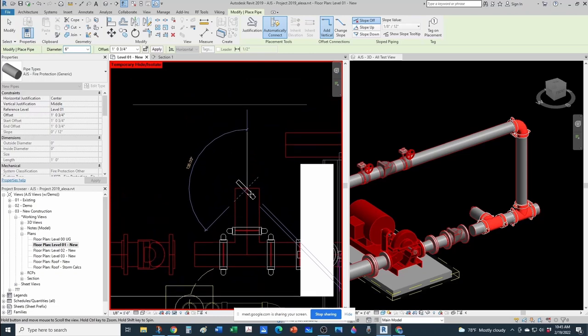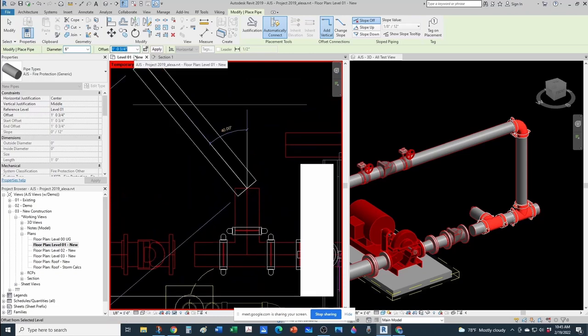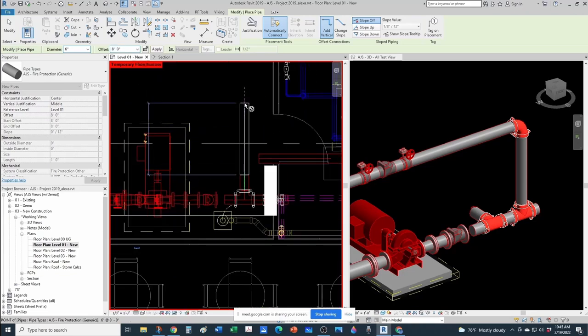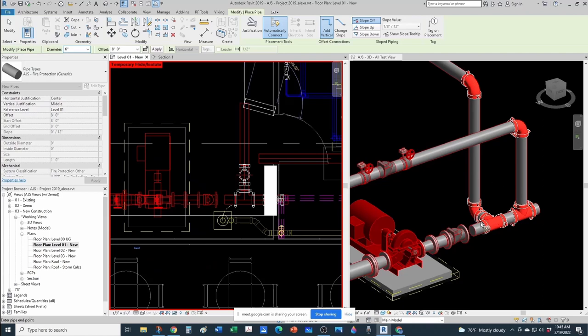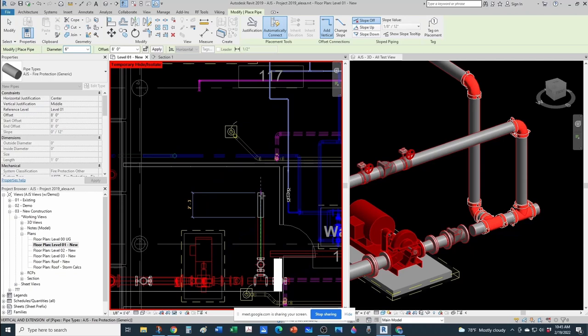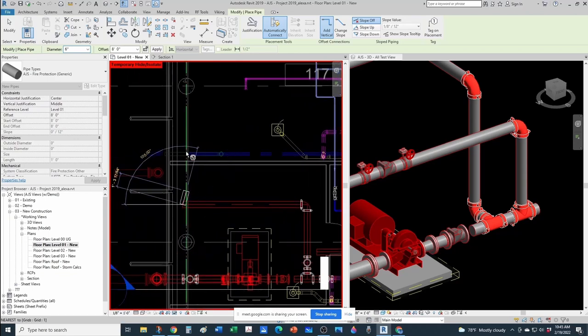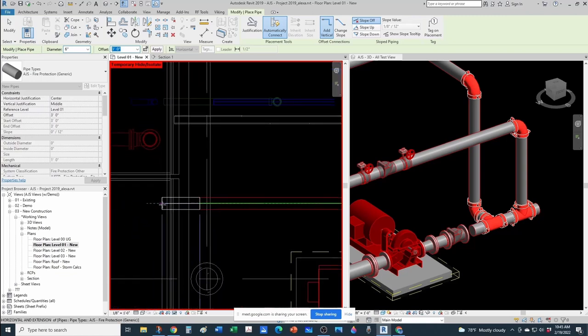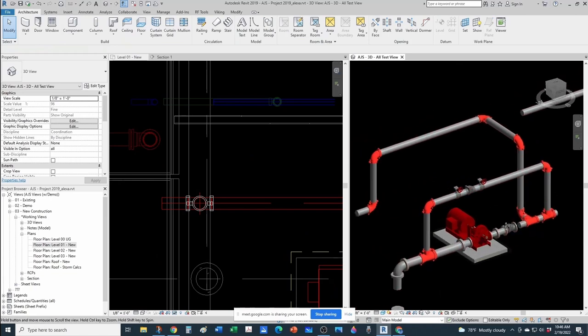Let me give myself some space to go up, and I'm gonna go up just head clearance, let's say 8 feet. 8 feet should be okay. And then I'll keep going this way, right? Notice that it introduces our riser automatically. Now I'm gonna go around the room a little bit, and probably I can come out for my test header. You need to obviously coordinate with your structural elements. So I'm gonna take it down to, let's say, 3 feet of elevation, and then go out to my test header, right? So it's a good idea to keep your 3D view as a live monitoring thing, even if you're not using it for piping, which I highly recommend.